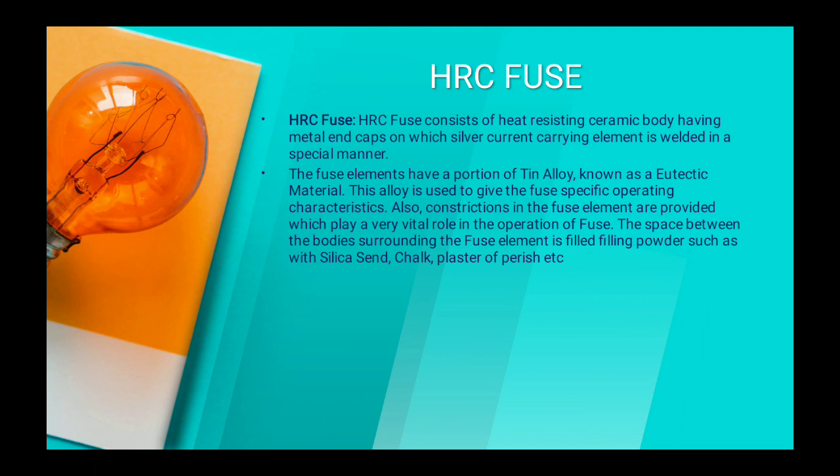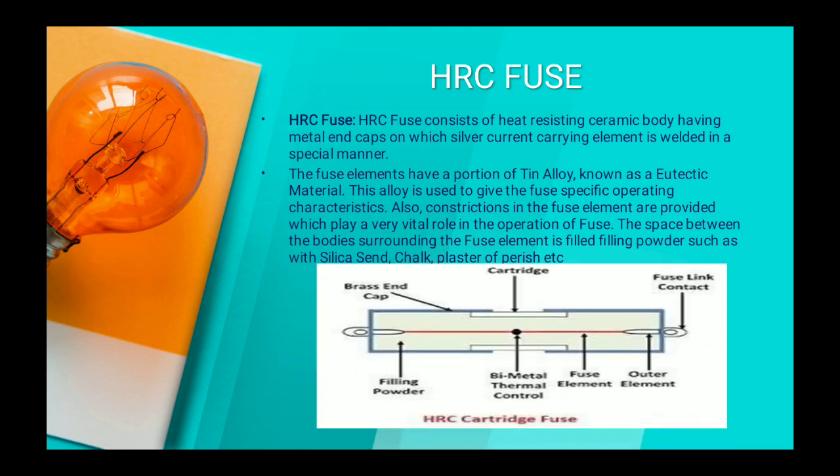Not only tin alloy but silver is also used in HRC fuse. The filling powder like chalk and silica sand are used as arc quenching medium and can absorb heat when the fuse melts or is heated. You can see an image of HRC fuse — the HRC cartridge fuse. The outer part is the end cap, and in the inner part there is filling powder, bi-metallic thermal control, fuse element made by silver, fuse link contacts, outer elements, and the cartridge. These are the various parts of HRC fuse.